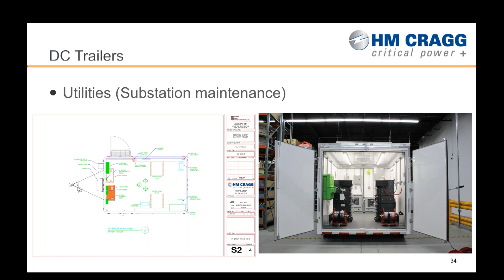They would purchase a DC trailer like this to be able to maintain the fleet of their substations and cell sites. So what's unique about these trailers is they are completely designed by HM Cragg. We do have supporting bracketry in the floor for underneath the batteries. We have supporting backers in the walls for all the equipment that's mounted. They come in 125 volt, 48 volt, or both voltage configurations for end users that require both voltages, or if they're good with the single 125 or single 48 volt system.